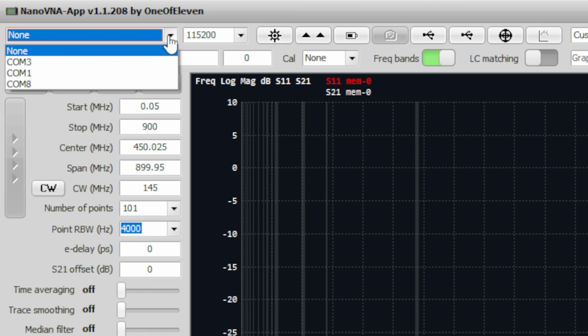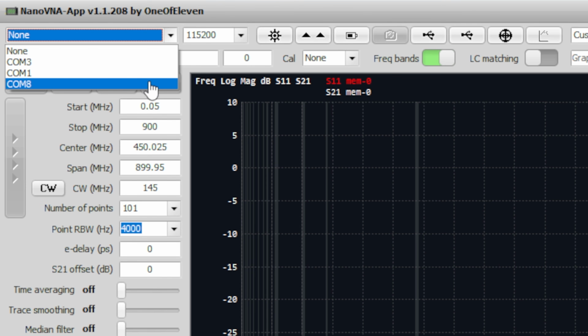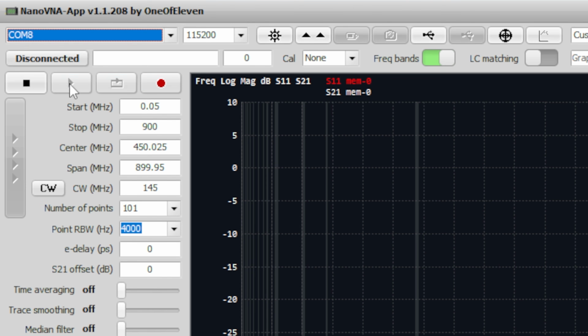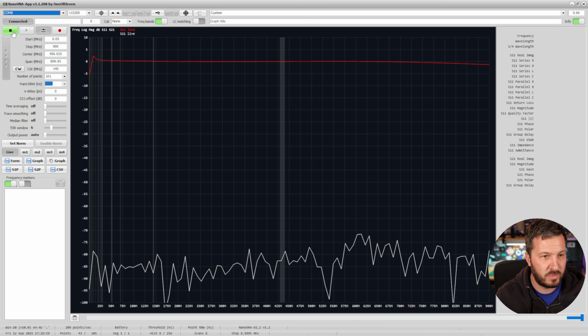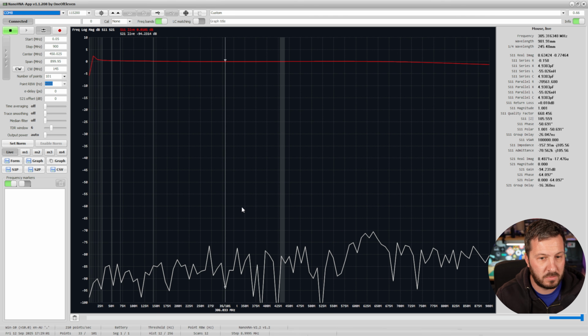So now that that's connected in, what we can do is go over to our COM ports. Now this has created a new COM port, which is COM port 8 here. And we can see that we've got a button here which says connected. It's automatically connected for us. And if we click continuous scan, all of a sudden we start to see some movement here in NanoVNA-App, and we can see that it's trying to scan through continuously over this frequency range.